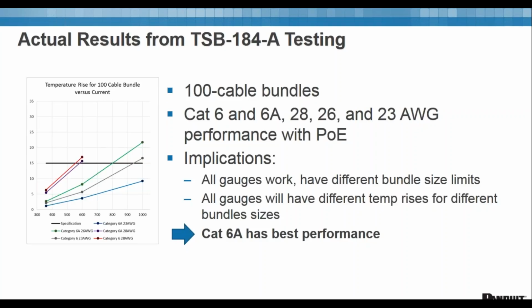So Panduit has a lot of guidance out there, but the first observation you can make is that 28 gauge cables absolutely support PoE. The second observation here is that Category 6A has the best performance. You can see here that all the other cable types for 100 cable bundles are over that 15-degree temperature rise. However, Category 6A with the matrix is significantly under it. So, what we are really telling people about it is that cables like Panduit's Category 6A are recommended for PoE due to the optimal thermal performance of those cables.